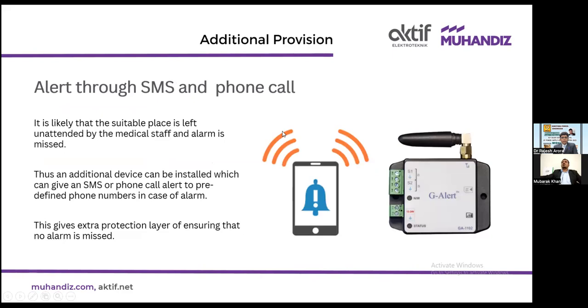Now there is another good to have product, which is an alert through SMS and phone call. We can have an IoT gateway installed inside the isolation panel, which can give a call to the maintenance and operation person that there is an earth fault and they should take action. Why is such a device required? There was a time when people were sitting at a place in their office or in the manned location, looking at all the alarms. But nowadays the engineers are moving continuously, and there are fair chances that when the alarm came, nobody was in the control room or the nurse station to attend to it. In that scenario, such a phone call will be very helpful.